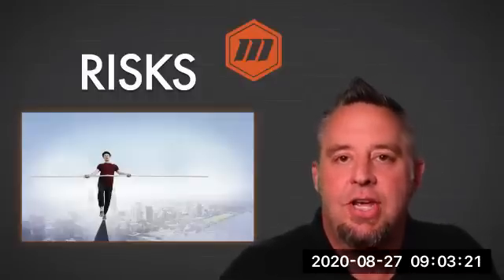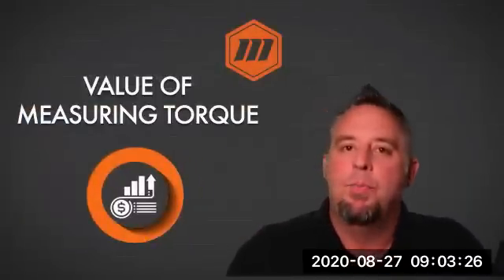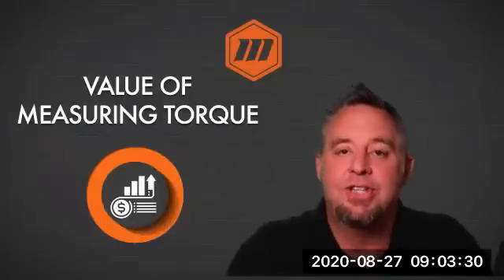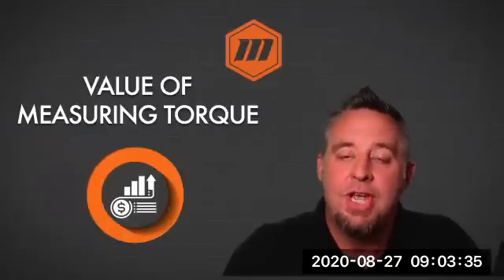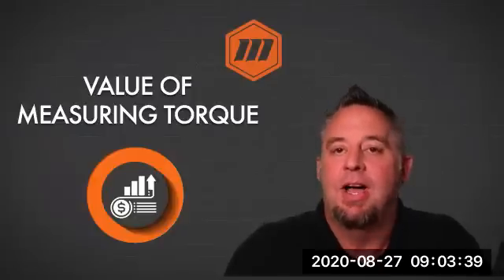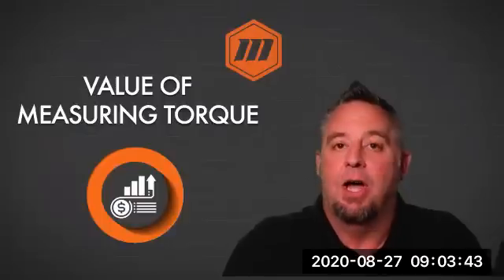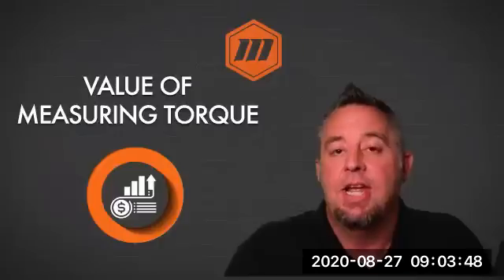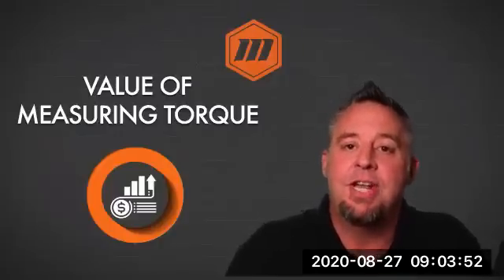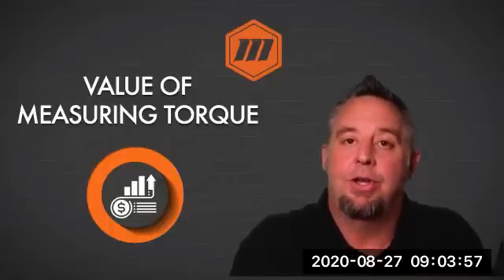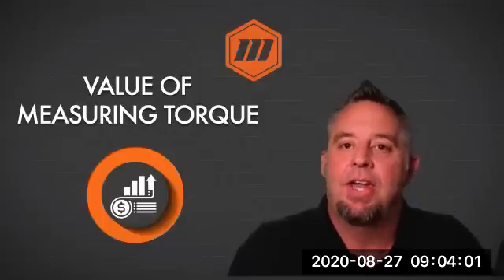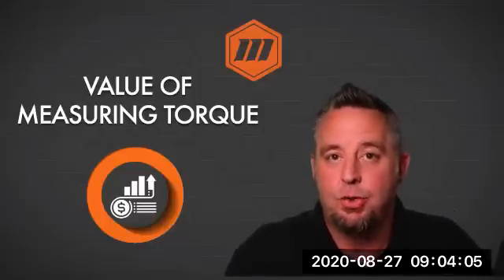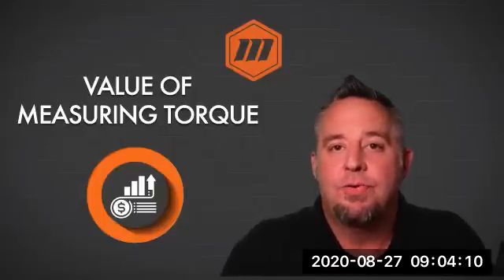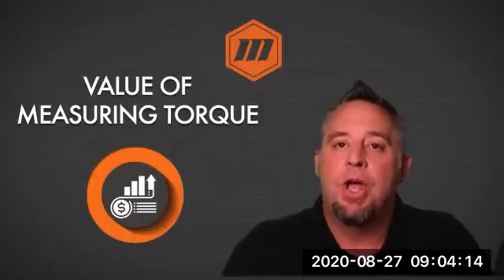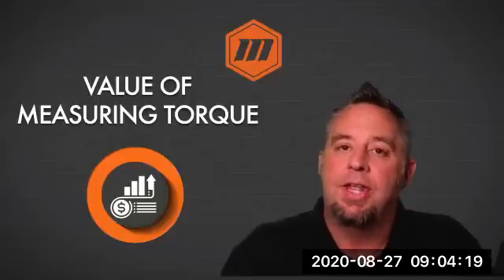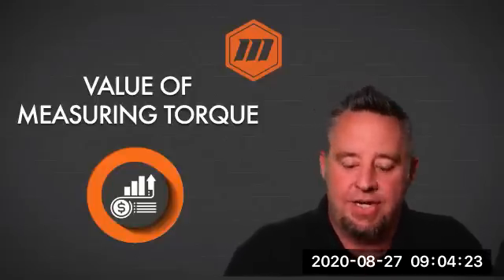And so how can torque sensors help with that? First, what are some of the values that come with measuring our torque values? First, it gives us the opportunity to evaluate our tools to make sure that they are performing the way that they're supposed to, that they're meeting the specification that they're meant to meet. We can also take a look at traceability. The analyzers and the sensors are traceable to a standard. Once those tools are then calibrated or tested using that sensor, that traceability is now moved to those specific tools. So we can evaluate how the tools perform, we can evaluate the traceability, and then we also have the documentation that goes along with that. So the value of having measuring equipment is great.